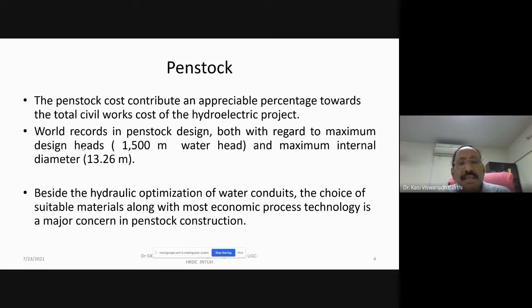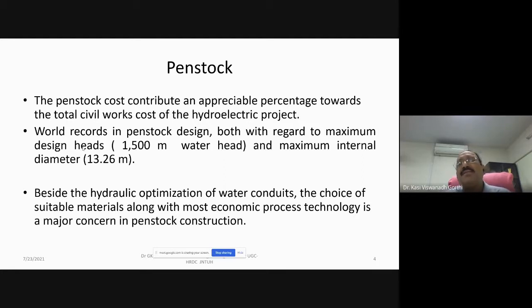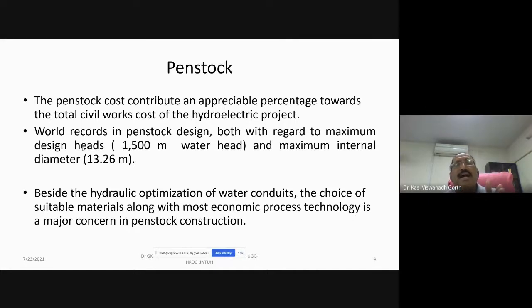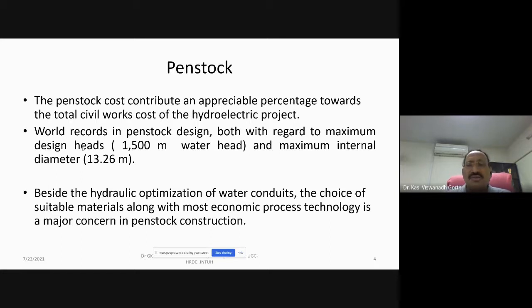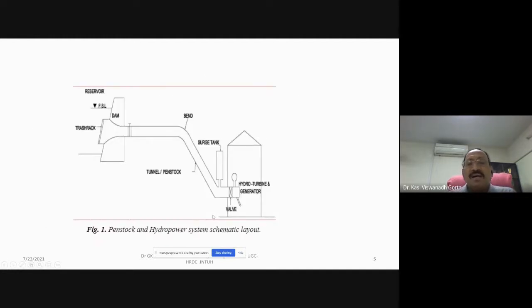World records in penstock design include a maximum design head of about 1500 meters — penstocks may be designed to carry water with a head of 1500 meters. The maximum internal diameter of a penstock pipe is 13.26 meters. For comparison, a building floor is about 3 to 3.5 meters high, so 13 meters is like four buildings — such a huge diameter may be there. The hydraulic optimization of water conduits, choice of suitable materials, and the most economic process of technology are major concerns in penstock construction.